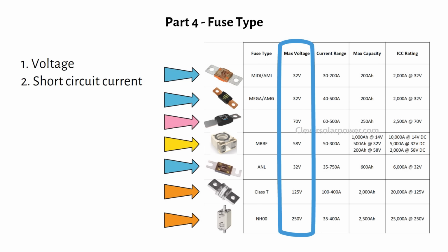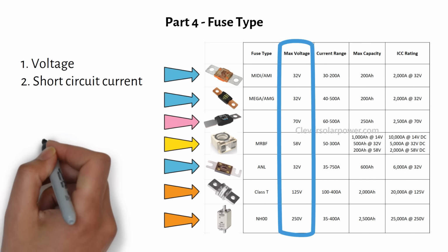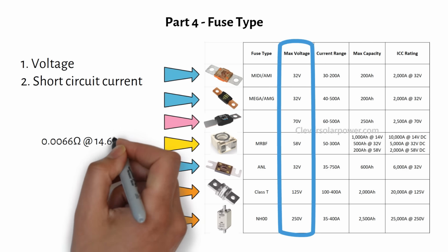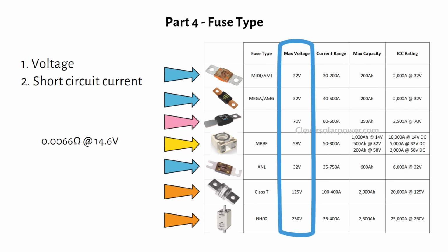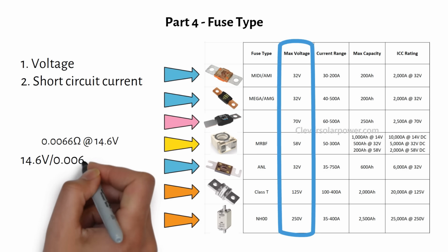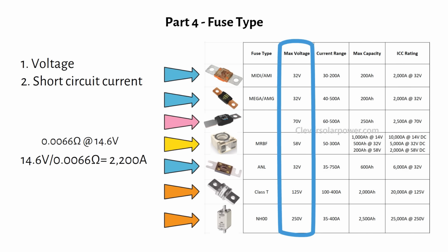If I take a 12 volt lithium iron phosphate battery and measure the internal resistance at the terminals, it's 0.0066 ohms, and the maximum battery voltage is 14.6 volts. Short circuit current is voltage divided by resistance, so 14.6 volts divided by 0.0066 ohms equals 2200 amps. That's what you're asking the fuse or breaker to interrupt in that short. Now imagine 2, 3 or 4 batteries in parallel. You can get fault currents in the thousands of amps. That's why I also recommend fusing each battery in parallel.